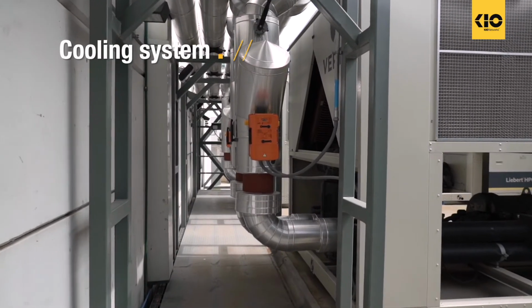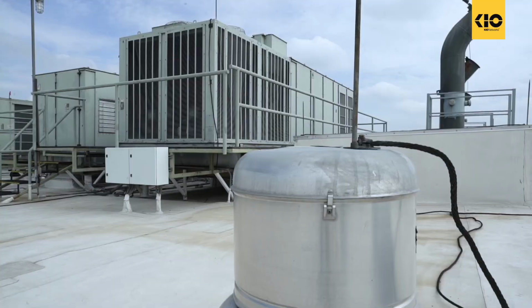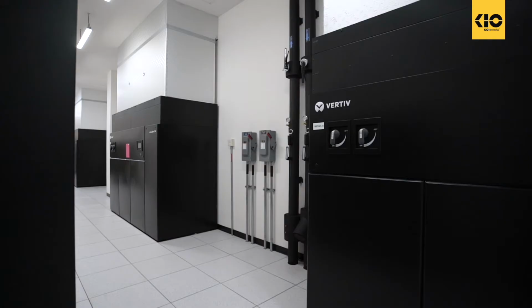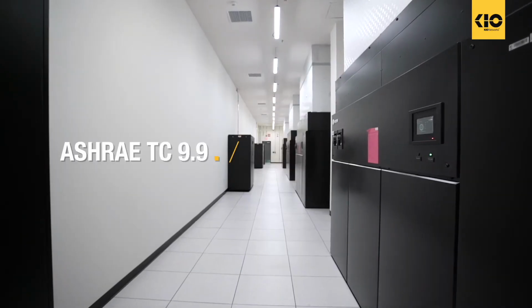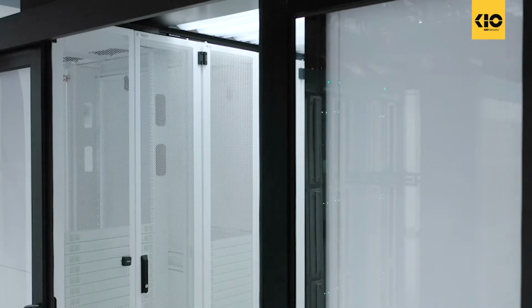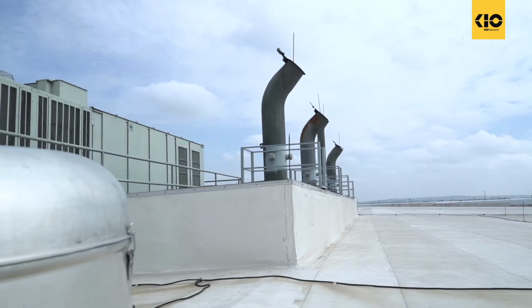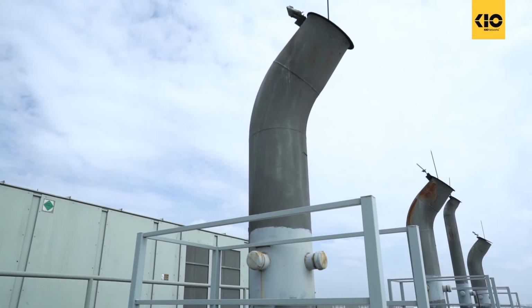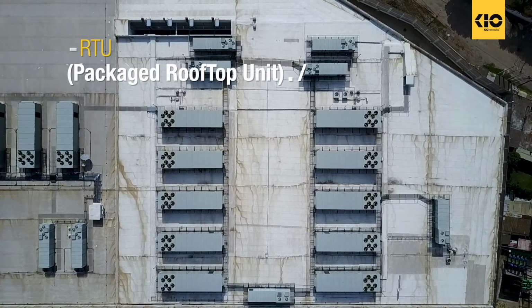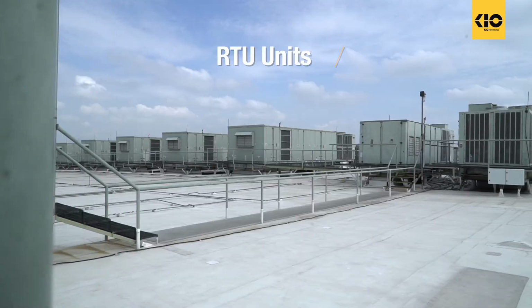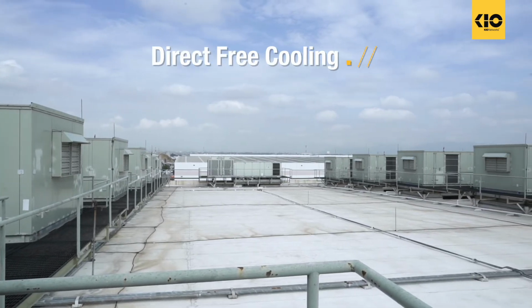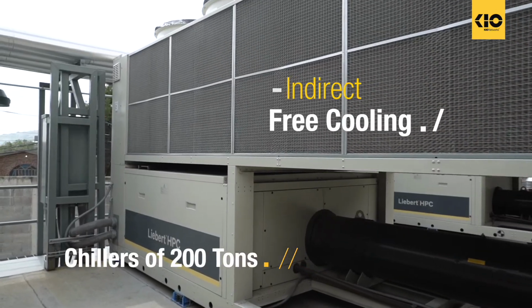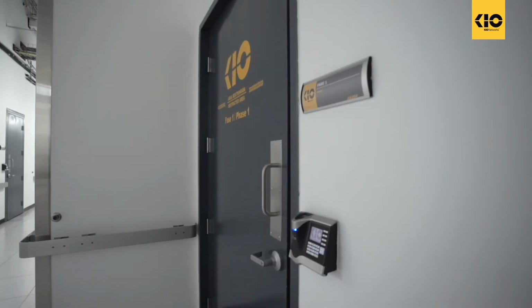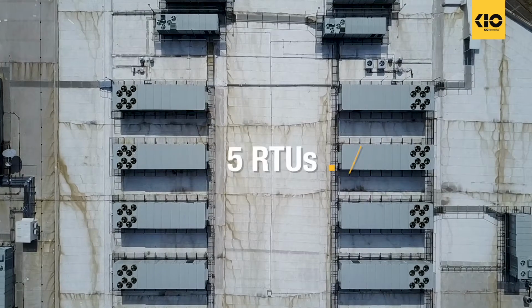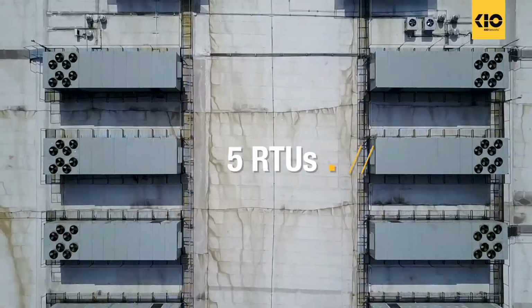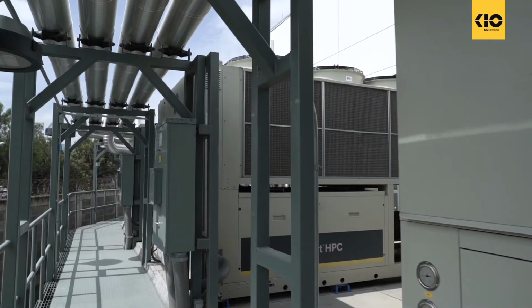A highly reliable and energy-efficient cooling system keeps IT equipment in optimal operating environmental conditions. Based on international standards and benchmarks such as ASHRAE TC 9.9, KIO data centers maintain airflow at the optimum temperature. It allows the extraction of heat that is mainly generated by the electronics of the IT equipment. KIO MEX5 has 2 high-efficiency cooling technologies: RTU units of 150 tons with direct free cooling, and air-cooled chillers of 200 tons with indirect free cooling. Each data hall, number 1, number 2, and number 3, is equipped with 5 RTUs with an N+1 redundancy topology. Data hall number 4 has 3 chillers with N+1 redundancy.